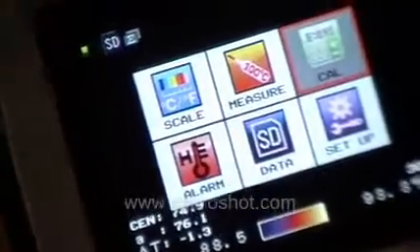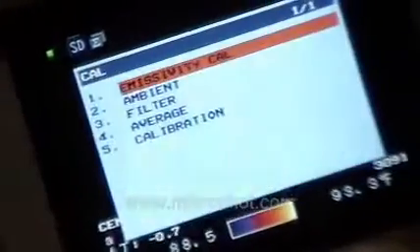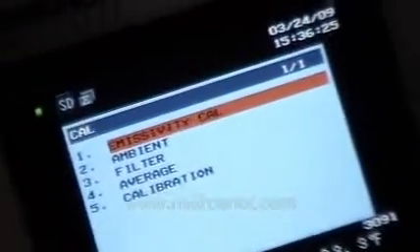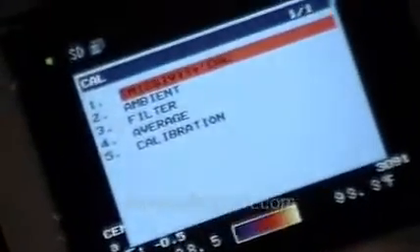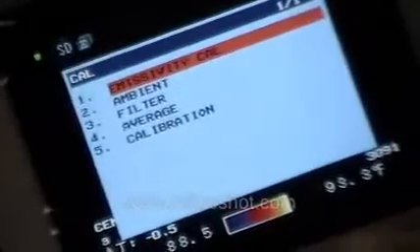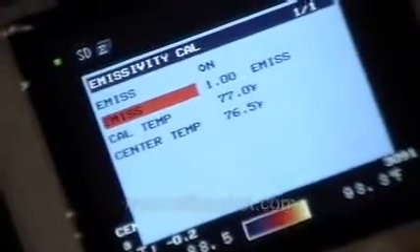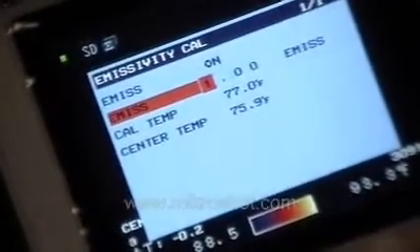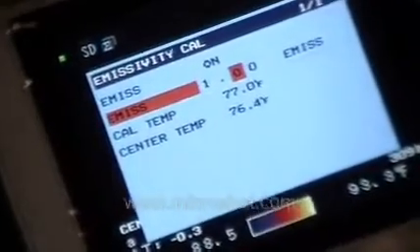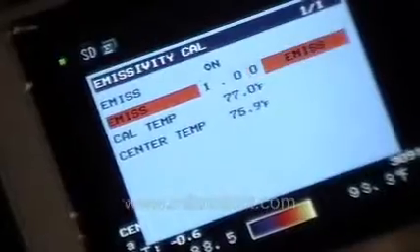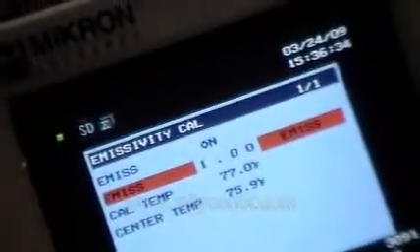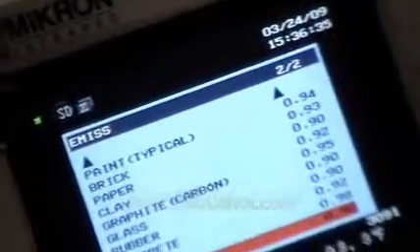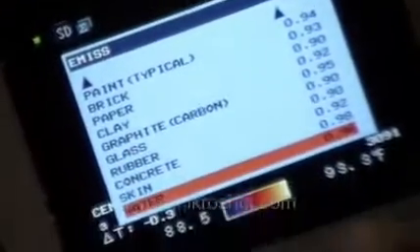The final menu item is the calibration function, where we can actually set emissivities for specific materials. Interestingly enough, this camera has a built-in emissivity table of 20 emissivity values for different materials.